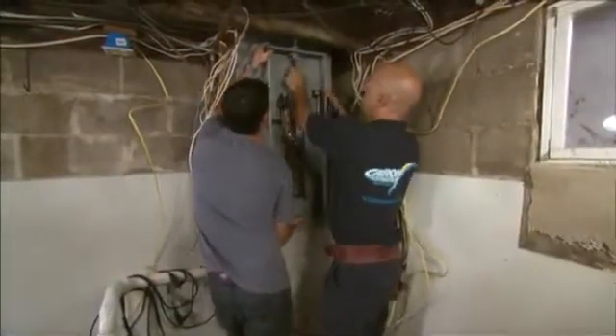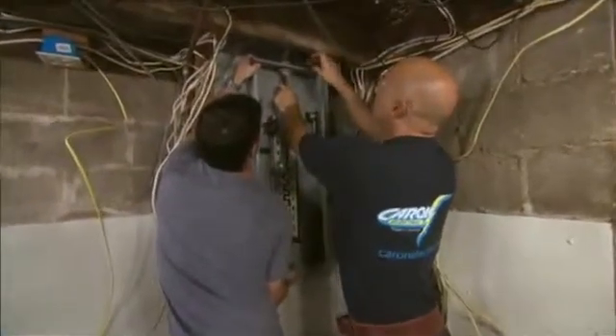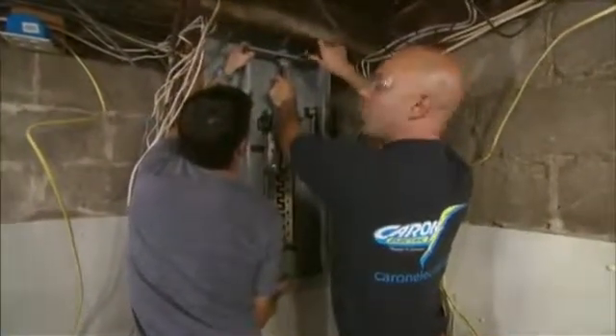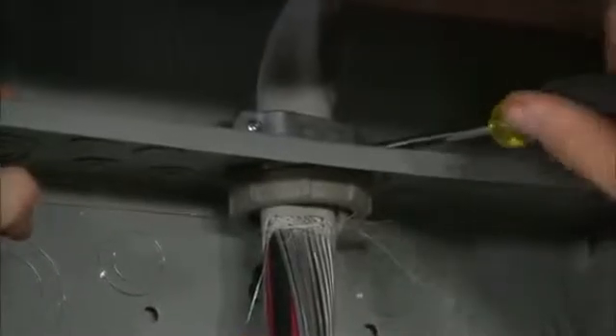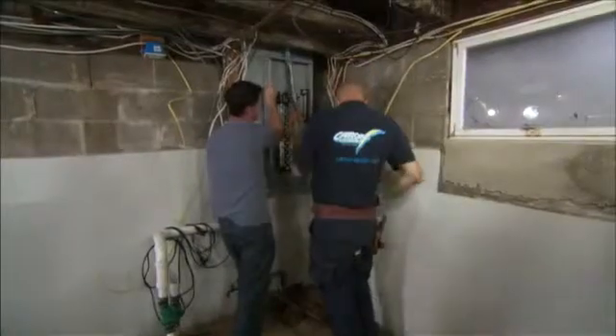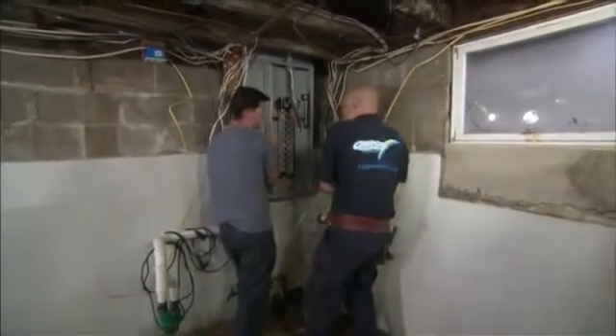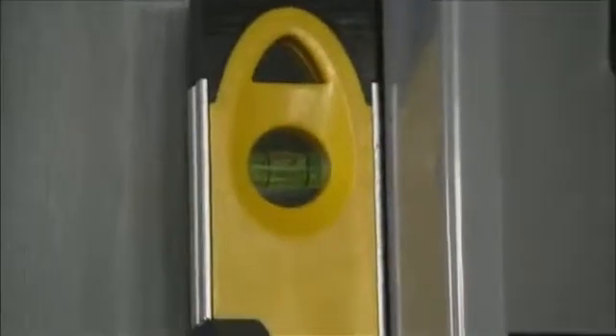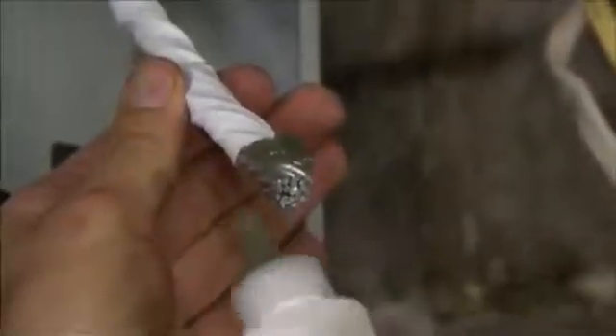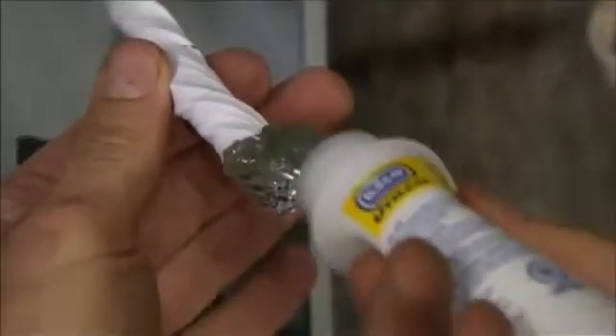Okay. We got the cable coming in from the outside. I'm going to go ahead and tighten this down. It's going to hold the cable in place. Okay. That's it. Now we're going to go ahead and level it and fasten it to the board. I'm going to take these bare aluminum wires, braid them together as one, which is going to be your neutral, and tie it into the neutral bus bar. This gel prevents oxidation on the wire.